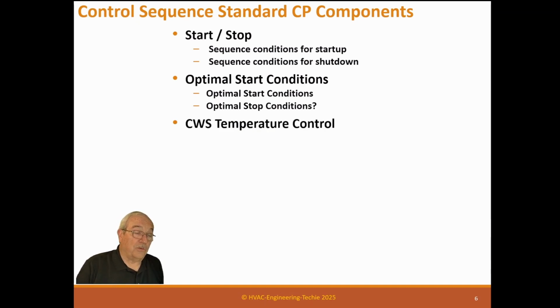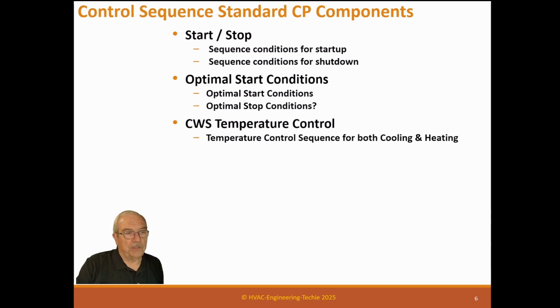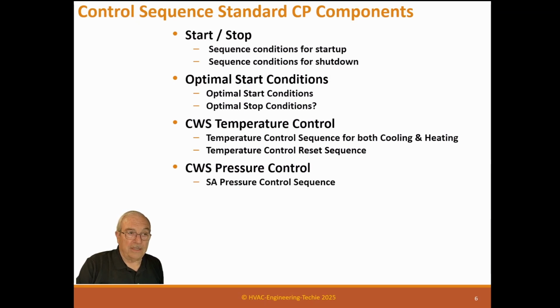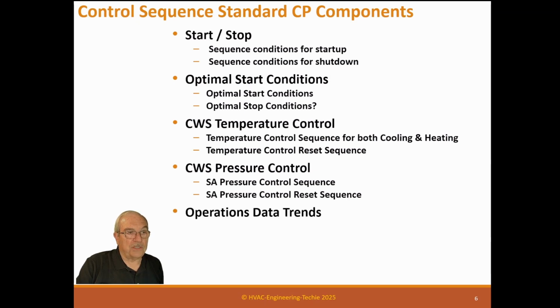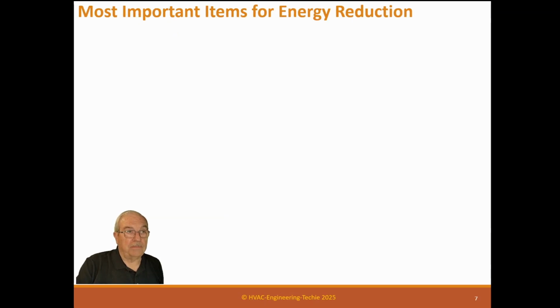Condenser water temperature control, that obviously we do. Temperature control sequence for both cooling and heating. Temperature control reset sequence, if it's going to be reset. Condenser water pressure control, we don't normally do pressure control, but you can. Supply air pressure control sequence, or supply air pressure control reset. Don't use that very often, but you could. Operational trend data for the operators, sensor data, runtime, and operational alarms. So all of these things need to be in the sequence. Now, engineers don't normally put in operational alarms and data trends, but we need the control contractor to build those for the operator so the building's ready to operate when it's turned over to him.